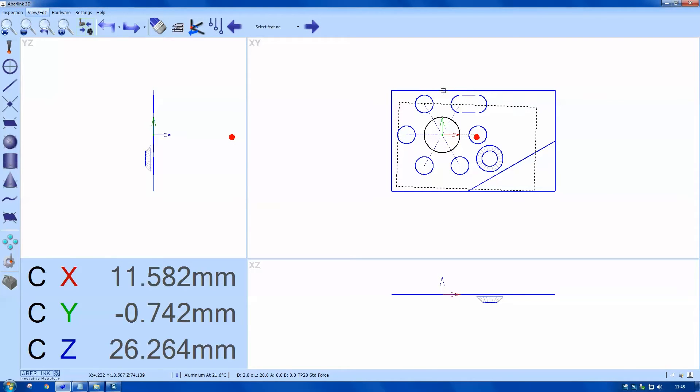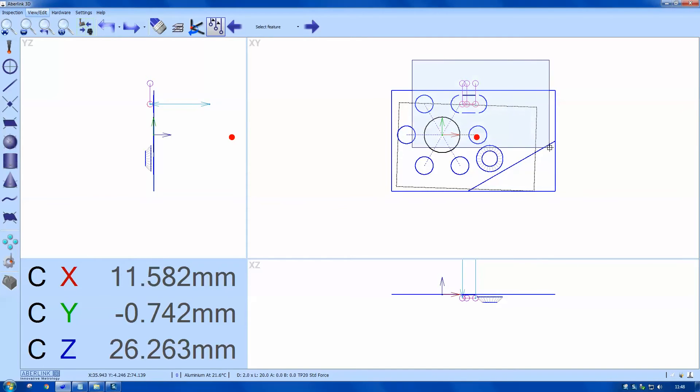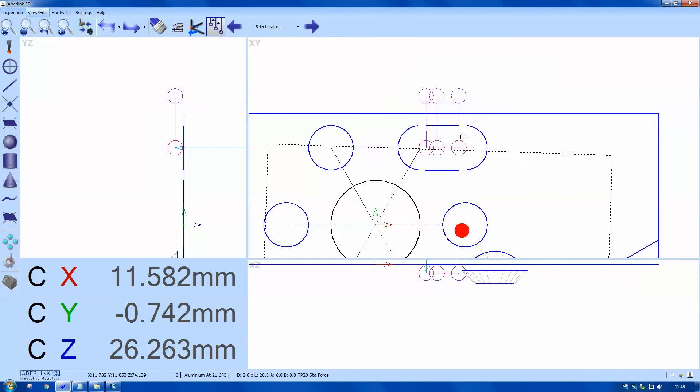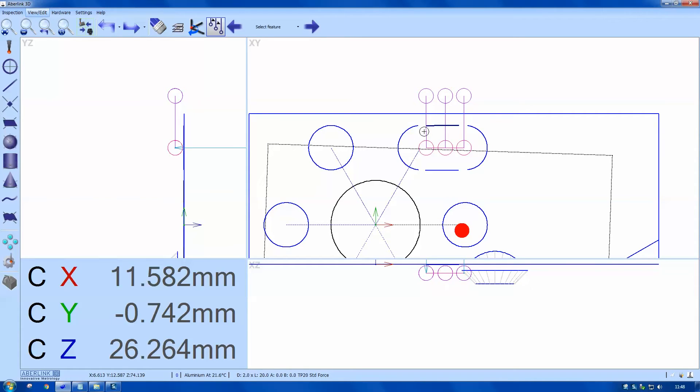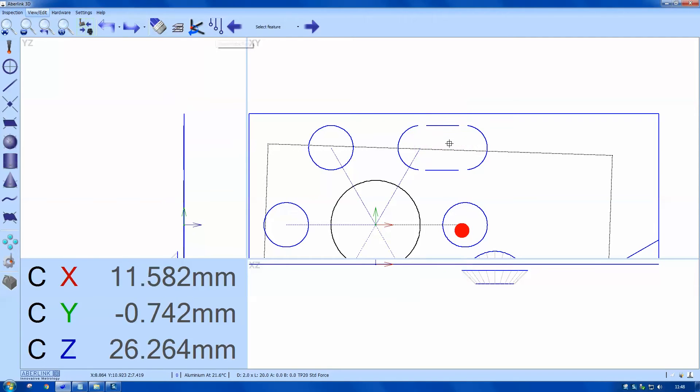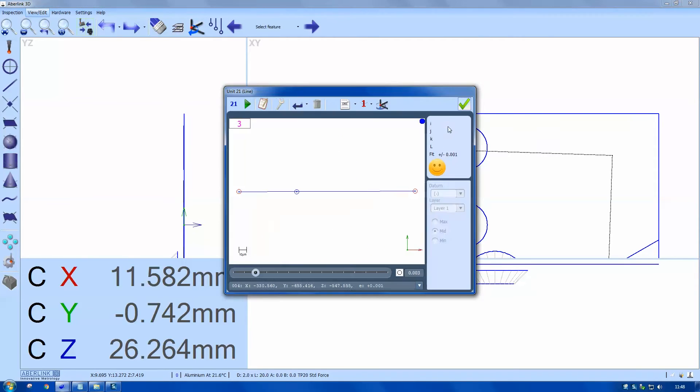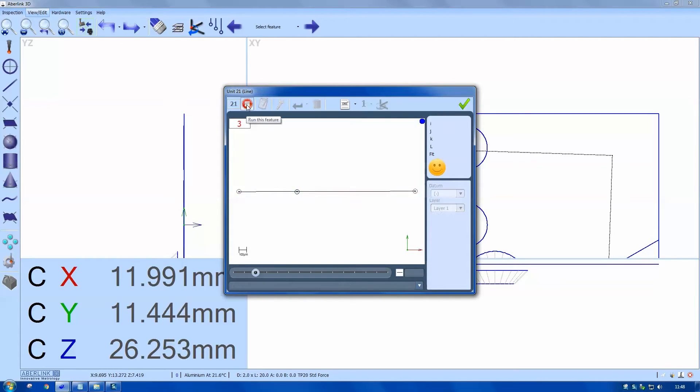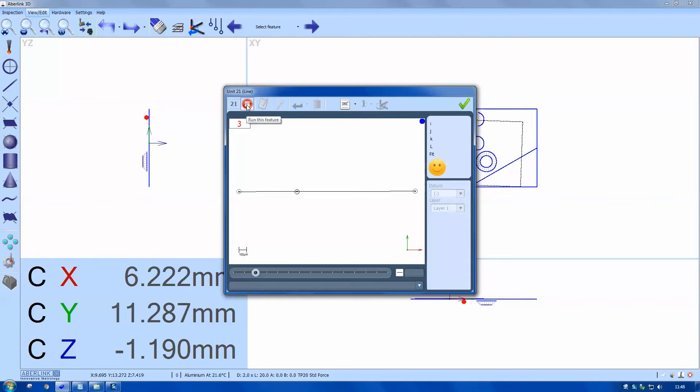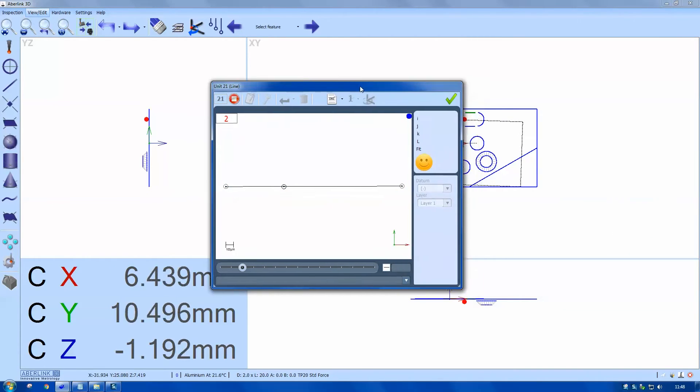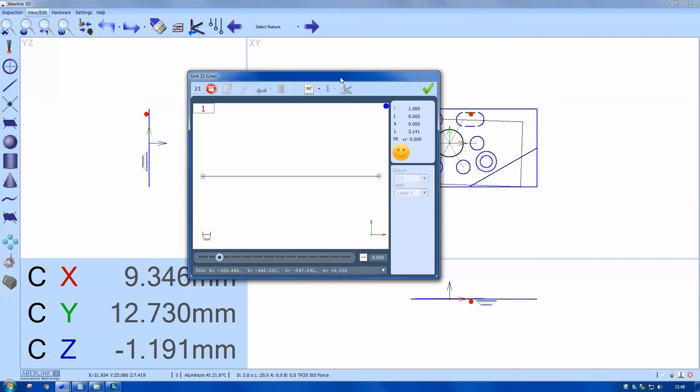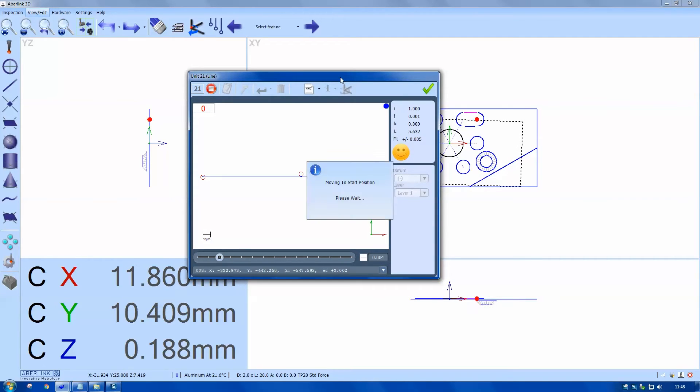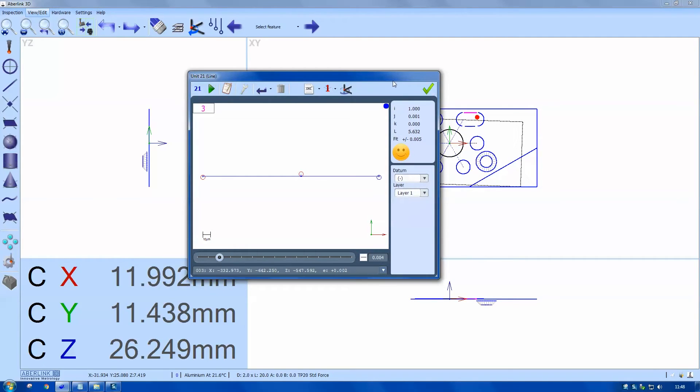Notice this line's a little bit shorter than I would like it, so I'm just going to physically drag the points across. I can use the mouse to reposition these probe moves to extend the line. I just want to play that feature back on its own. So edits are very simple.